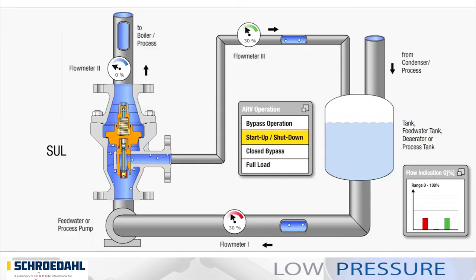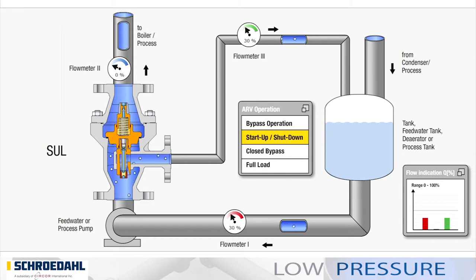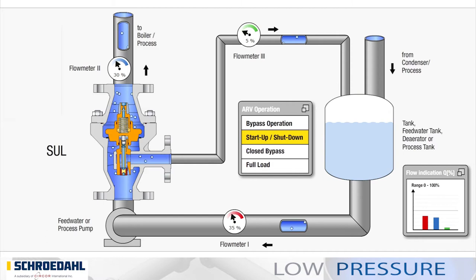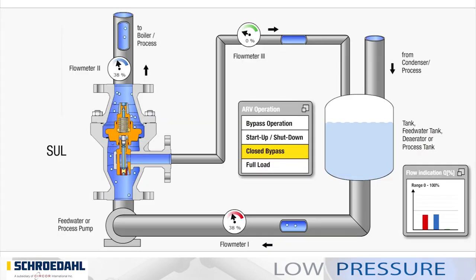When the plant is started, the valve responds by supplying the flow rate necessary for the production process, entirely through its design, without the measuring units required in conventional valves. The check valve lifts and opens the valve. The medium passes through the SUL to the turbine, or to the downstream process. The difference between process and pump volume flow is balanced by the bypass. When a predetermined process volume is reached, the bypass reaches its closed position.